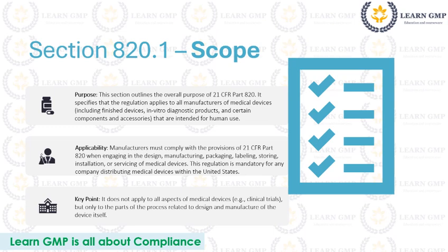Applicability. Manufacturers must comply with the provisions of 21 CFR Part 820 when engaging in the design, manufacturing, packaging, labeling, storing, installation, or servicing of medical devices. This regulation is mandatory for any company distributing medical devices within the United States.